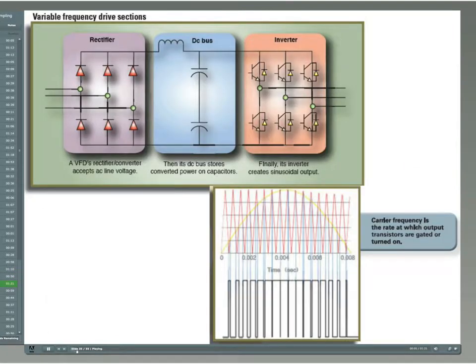Rectifier converter. One of the 3 primary sections of a VFD's main power circuit, and first in terms of power flow. Incoming AC line voltage is rectified to DC voltage in the converter section, which consists of diodes, silicon-controlled rectifiers, SCRs, or insulated gate bipolar transistors, IGBTs, connected in a full-wave bridge configuration. DC bus. The second primary section of a VFD's main power circuit chiefly consists of capacitors that store power rectified by the converter.